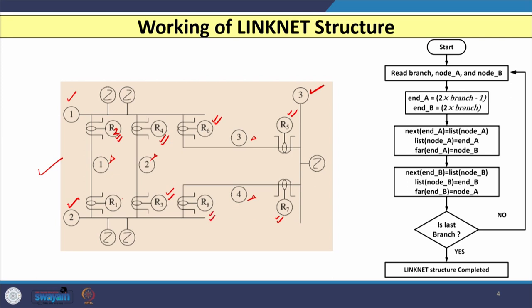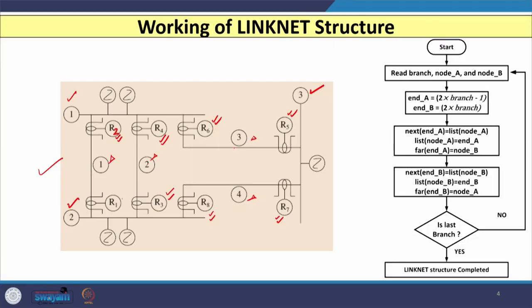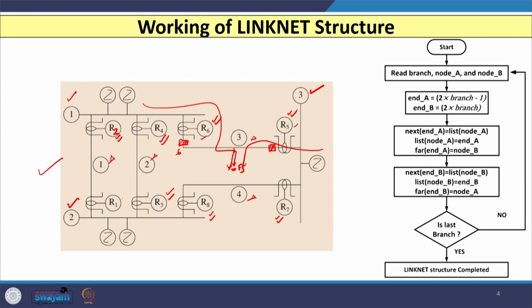For each branch we need two relays. For example, if there is a fault at F3 in branch 3, the fault current flows via two paths. That fault should be detected by both relay R6 and relay R5. R6 sends a signal to circuit breaker 6 at substation 1, and R5 sends a signal to circuit breaker 5 at substation 3. Both circuit breakers open, disconnecting the fault. Hence, for four branches, eight relays are needed.